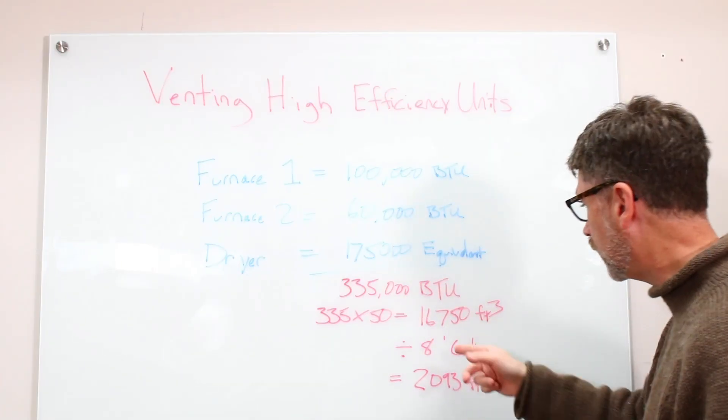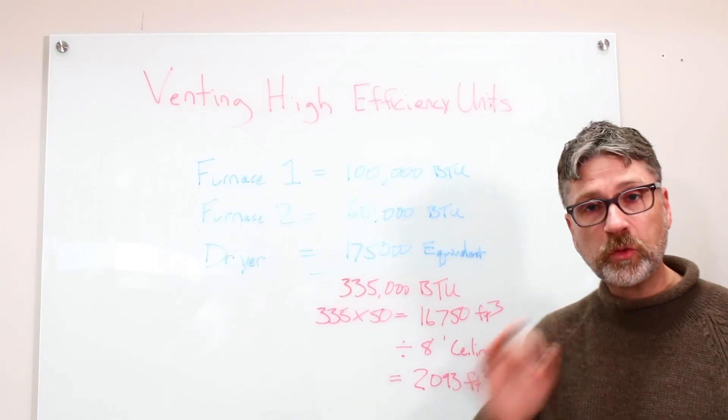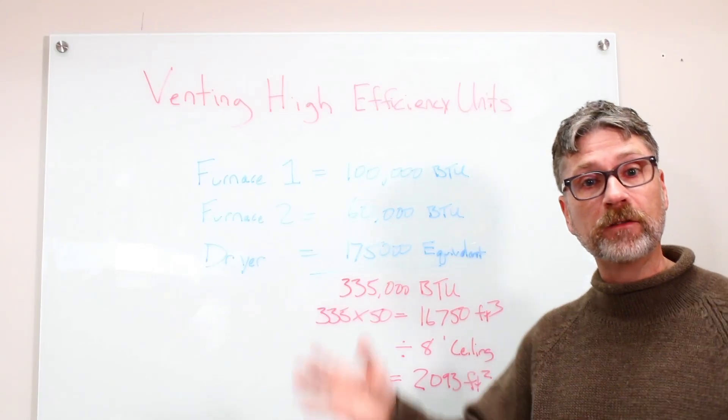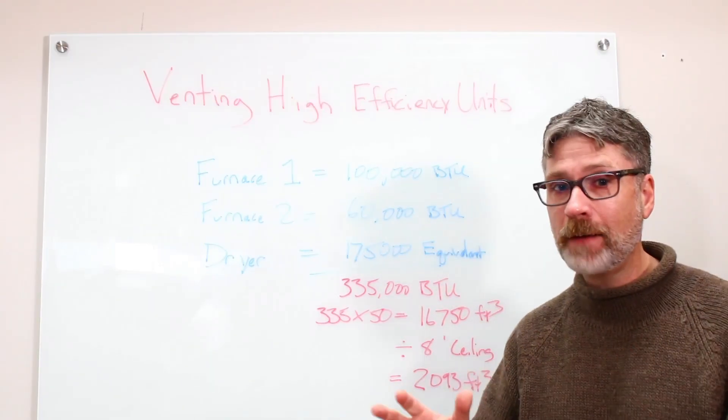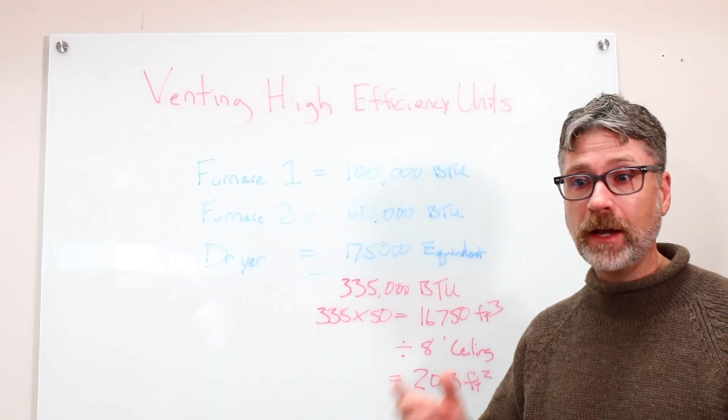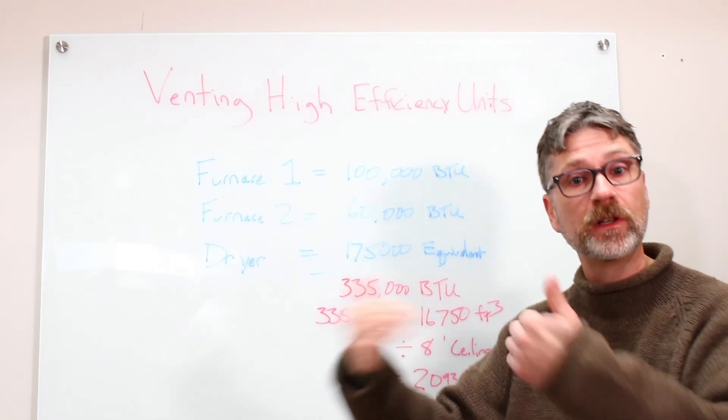Multiply 335 times 50 cubic feet per 1,000 BTU, and we know that we need 16,750 cubic feet. Now, if the ceiling in that area was eight foot, divide by eight, now we have almost 2,100 square feet of free area required to run those three appliances. If it's not that big, and it wasn't, then what you need to do is pipe the combustion air on those furnaces from outside.